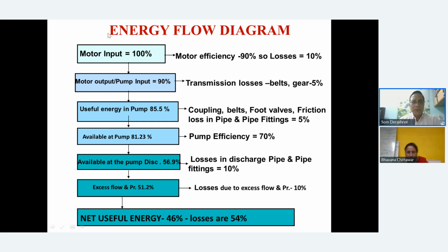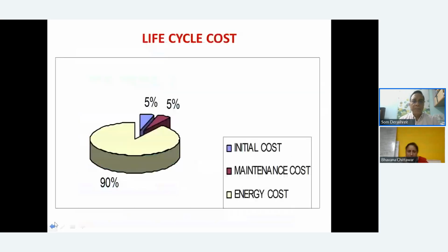At that point, what was 100 input to the motor, we are now ended up with 51.2%. And if you consider that, normally you always have a margin of 10% on flow, pressures, etc. So you end up, basically, what was useful as 100 units of energy, you're getting only 46% as the output in terms of the hydraulic power.